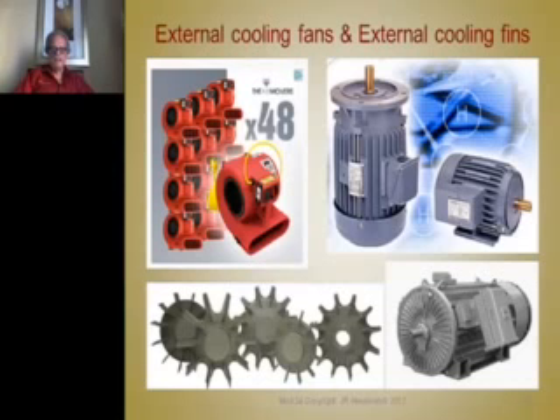Now here are some examples of fans and serious cooling fans. This is a motor and a centrifugal blower or suction device. These are the type of fan blades that go on the end of a shaft. These aren't inside the frame; they're on the outside. That would be in an enclosure like that, which would blow the air down over the fins. Here's another example. This has fins. That's got a can over there. Same with this one. One of these fan blades is mounted on the end of the motor in the back. That greatly improves the thermal capacity of these machines.